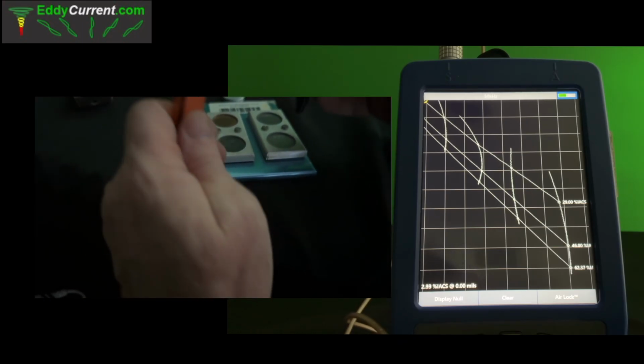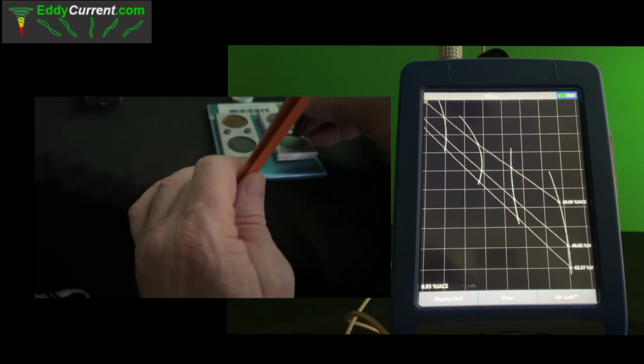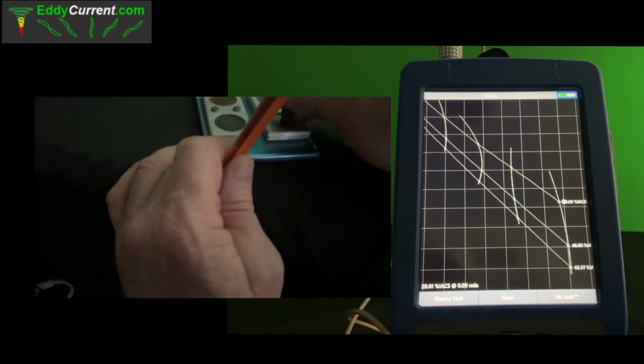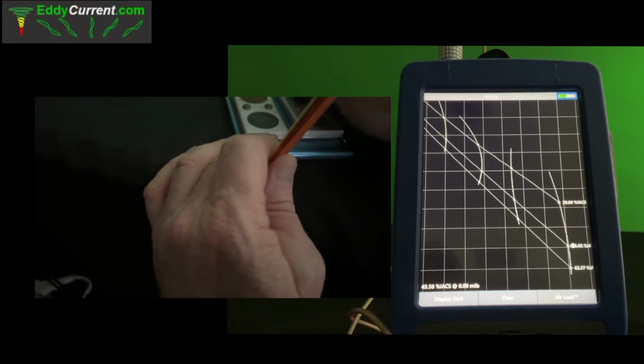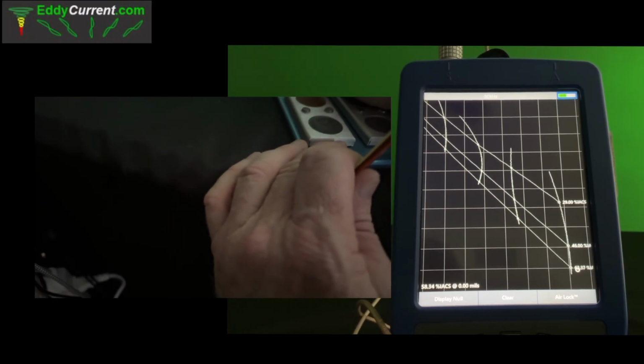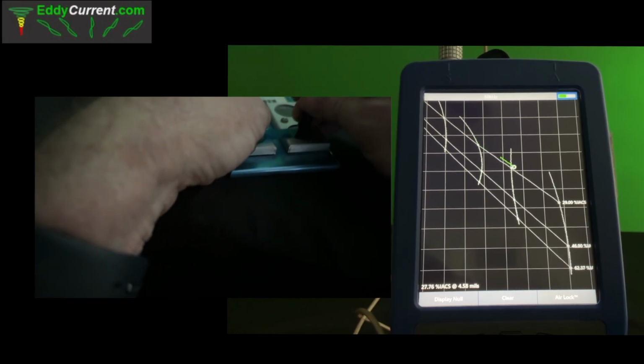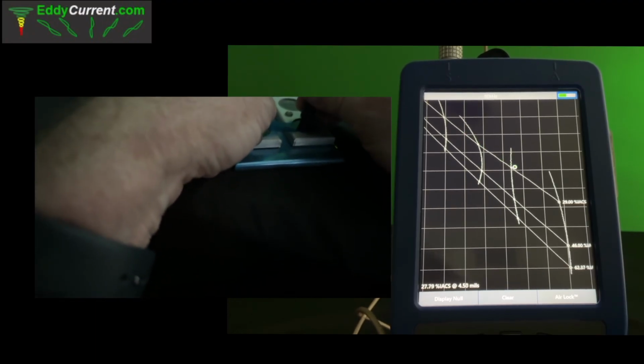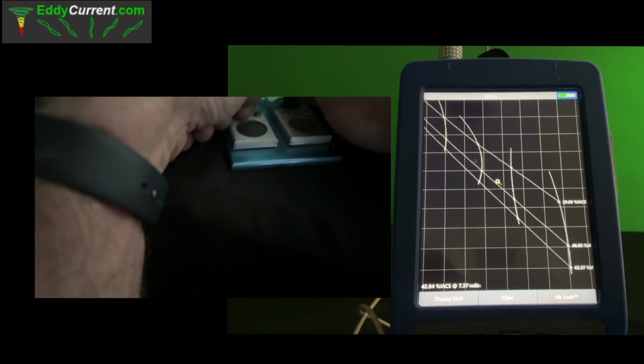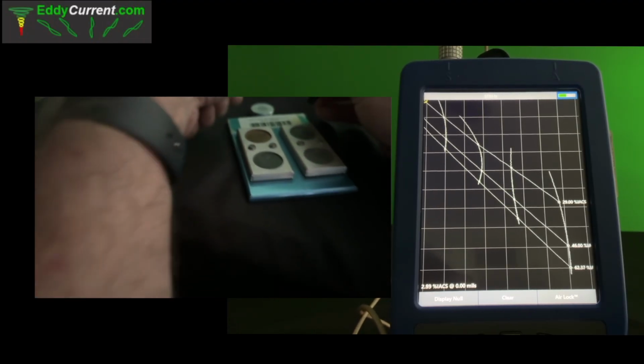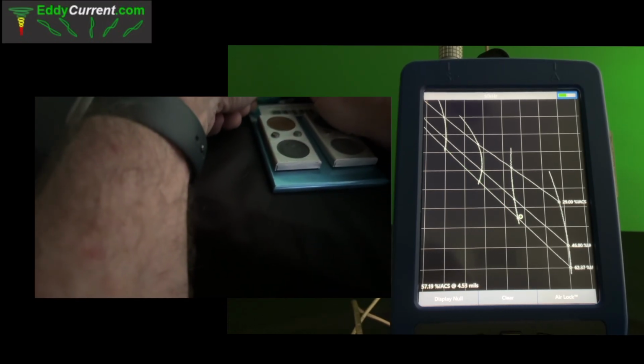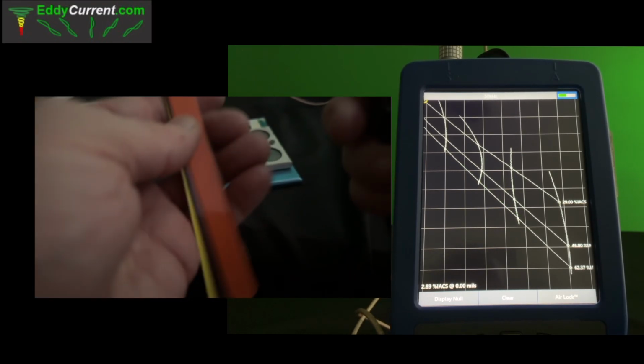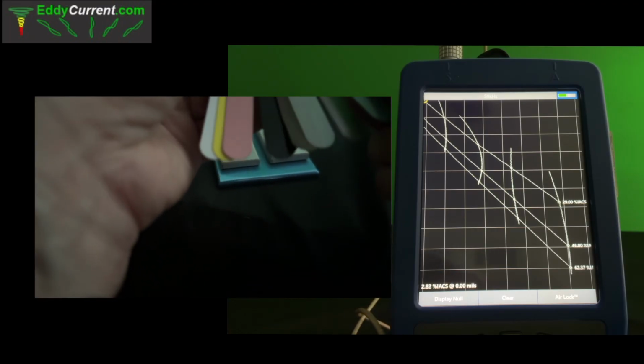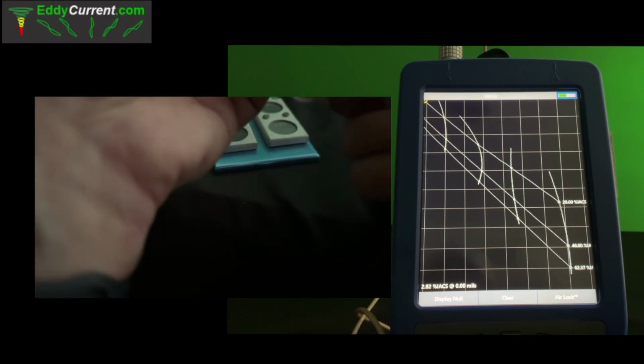So here I'm going to do the three materials without any shims. So that one reaches the initial point. Here's our 46%, our 62.37. And when we put in the first blue shim, it would be 5 mils on the 29%. Right about to that same point. This will be the 46%. And so it's pretty repeatable. Here's the 62.37. There you go. So by storing these known vector points, it tells you what the conductivity of your material is and what the approximation of liftoff is.